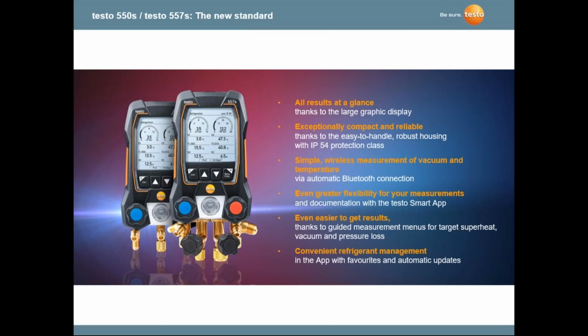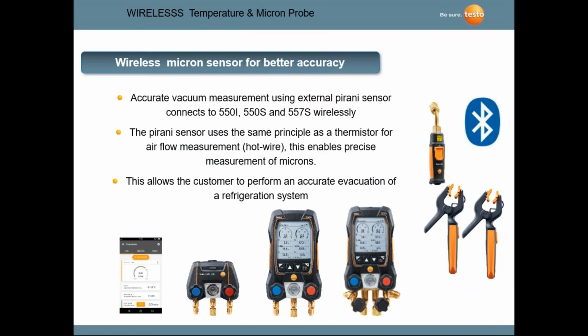So as you can see here, completely wireless, quick and easy to use, nice handheld package, very durable. Everything is wireless on this instrument. So your 2 pipe clamp probes that you see there communicate to the instruments below. There's a 550S 2-valve and there's a 557 4-valve. From the instrument, the data is going into your smart device, whether it's an Android device or an iOS device, a cell phone, or a tablet. If you look at the top there's a vacuum sensor. The vacuum sensor is also wireless.